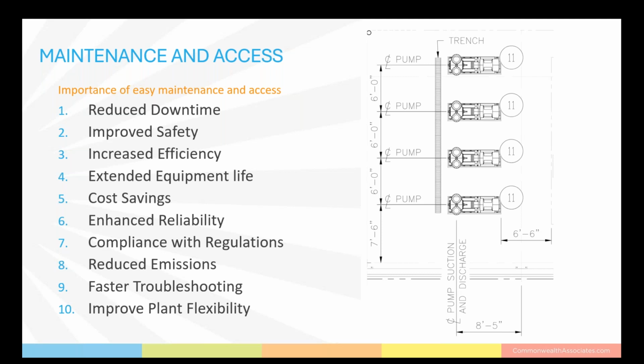While there may be some special circumstances for large maintenance and access clearances, in general, 3-foot minimum around any piece of equipment is a good rule of thumb. Although, as we learned in the electrical section, space requirements are driven by voltage rating of the equipment and NEC requirements. In this example on the right, there's 3 feet of space between each pump. Where space allows, I try to leave enough room off the motor side of the pump that equals the distance from the end of the motor to the end of the coupler at the pump side, in case one of the motors needs to be pulled and wheeled out of the area. In this case, I had 6.5 feet of clearance.